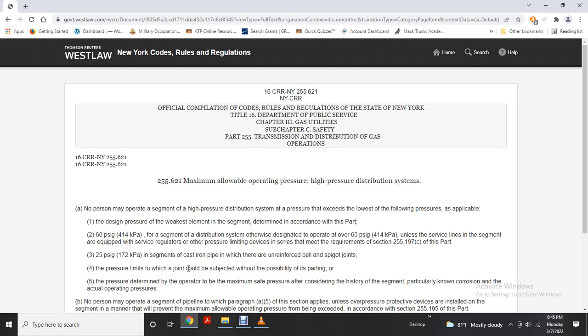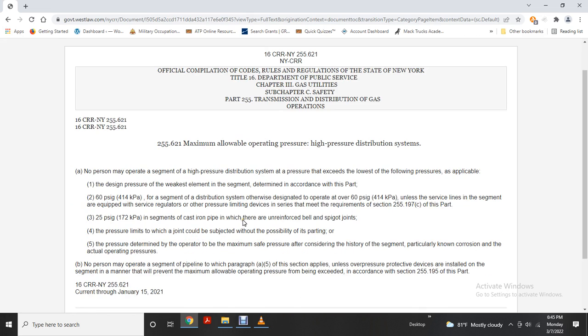Maximum allowable operating pressure, high pressure distribution. No person may operate a segment of a high pressure distribution system at a pressure that exceeds the lowest of the following applicable pressures: the design pressure of the weakest element of the segment, determined in accordance with the part; 60 psi gauge for a segment of a distribution system otherwise designed to operate over 60 psi gauge, unless the service line is equipped with a regulator or other pressure limiting device that meets the requirements of 255.197(c); 25 psi gauge for segments of cast iron pipe in which there are unreinforced bell and spigot joints; and a pressure limited to the joints, which can be subjected without possibility of parting.